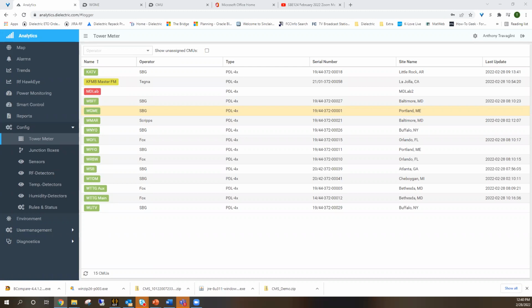So this unit will monitor your forward and reflected power on channel, as well as give you the TDR. So when there's no forward power, your directional coupler reading won't be accurate. It probably gives you an alarm saying you're probably like a 4-to-1 VSWR, or even negative, meaning you probably have more coming back down the line than going up the line.